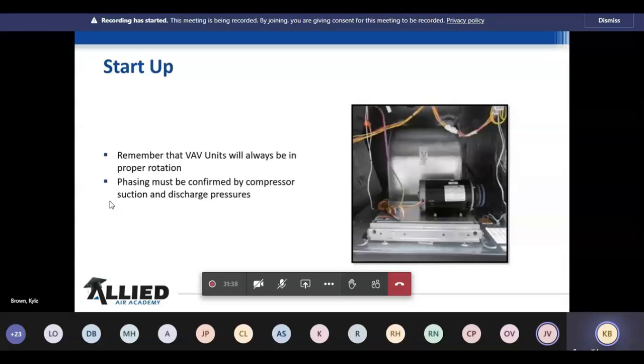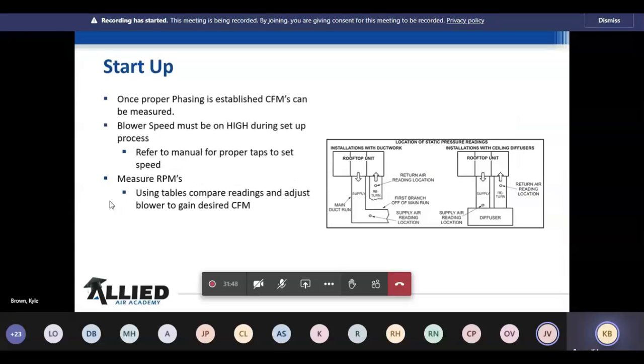We're going to make sure it's all cleaned up, all tidied up, and that the blower belt is lined up as well. So when we do these, there's several different ways of checking static pressures. And I've always said this on this slide, in the real world, it's probably not going to happen this way, but these are the ideal places to check for your static pressure. Now, I get it. Not in all cases are you going to be able to do this. There's places on the units, especially on the smaller ones, where you have the two side panels for horizontal discharge.